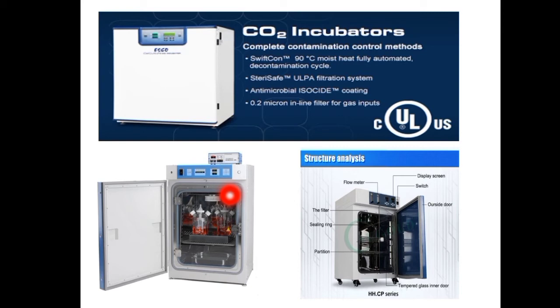So the air coming in flows through sterile filters and must be distributed evenly throughout the whole interior. The challenge lies in creating this quality throughout the entire interior to ensure a uniform supply of CO2 for all the samples at constant climate and humidity conditions.